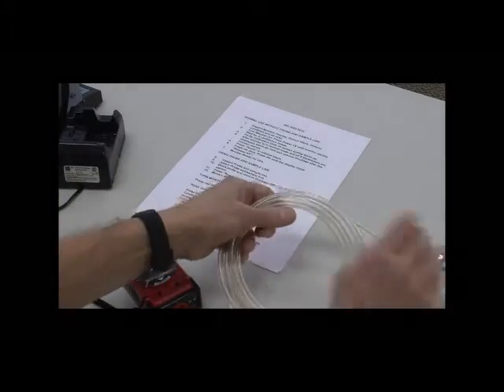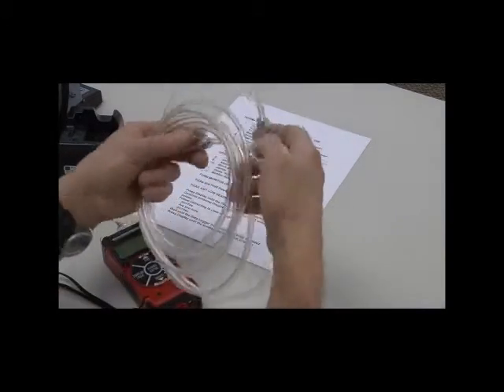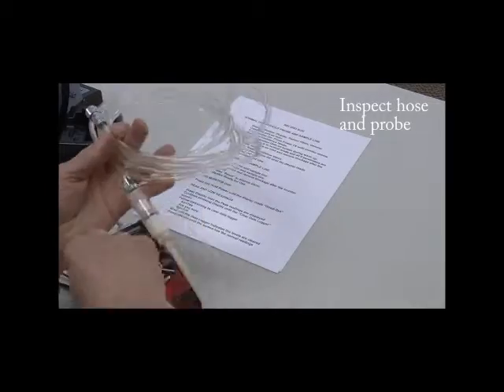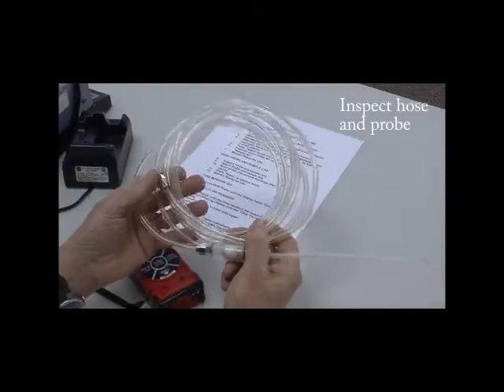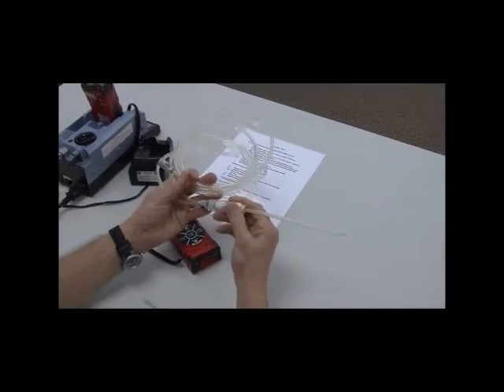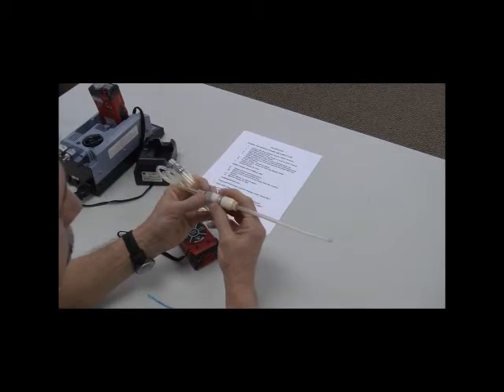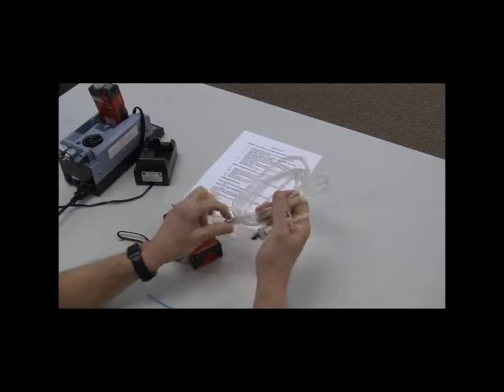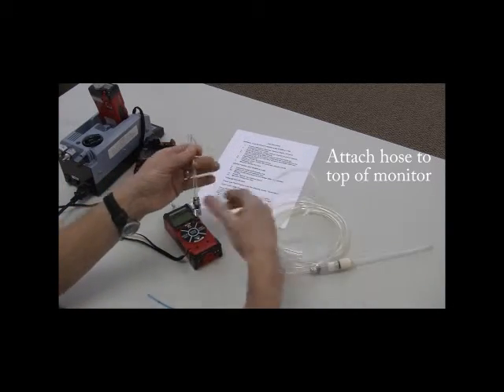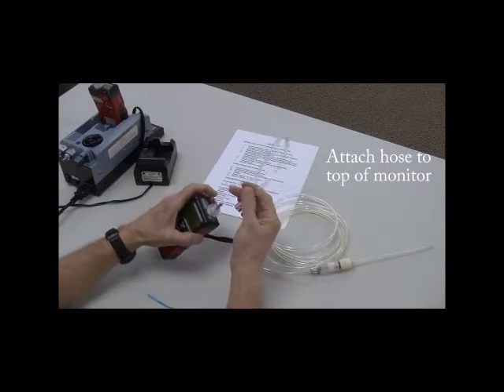So the next thing I need to do is look at my sample hose and probe and make sure that they're working well. I need to inspect them to make sure they're not contaminated, dirty, and that they're put together properly. Once I've done that, I'm going to attach the hose to the top of the monitor.